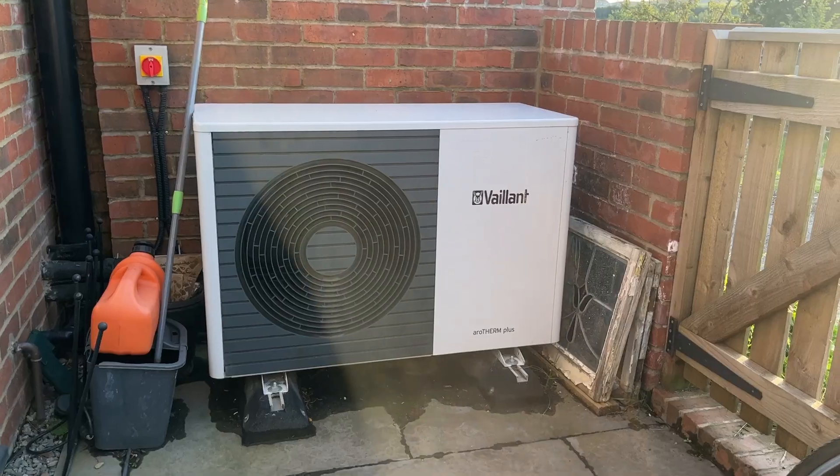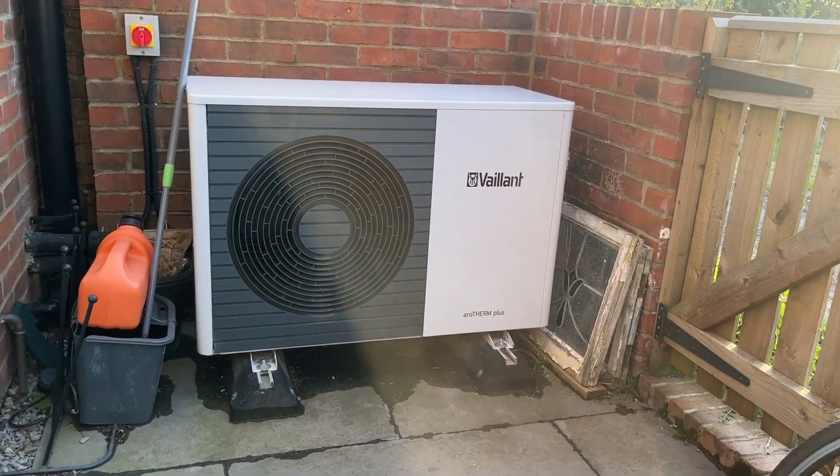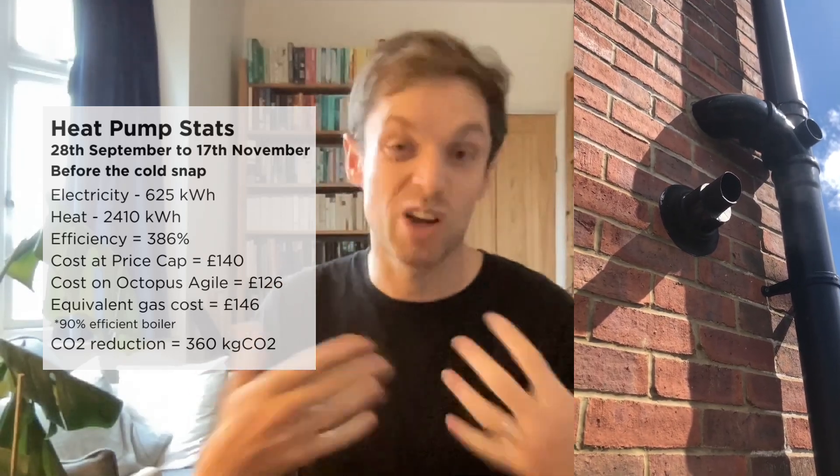Segment one: 28th of September to the 17th of November, just before it got really cold. Over that time our system efficiency averaged 386% — a coefficient of performance of 3.86. That means for every kilowatt hour of electricity used, we delivered 3.86 kilowatt hours of heat. We used 625 kilowatt hours of electricity, which would have been just under £140 at the price cap. This electricity delivered over 2,400 kilowatt hours of heat. A 90% efficient gas boiler delivering the same heat would have used 2,680 kilowatt hours of gas, costing £146.86 at the gas price cap.